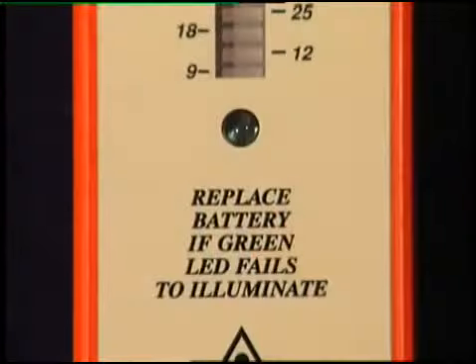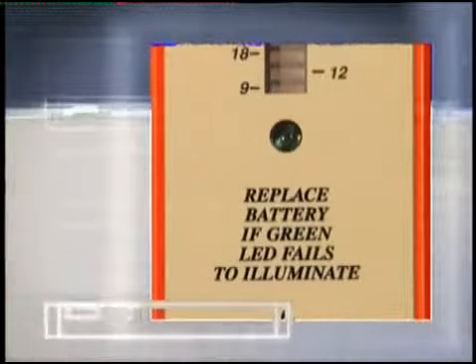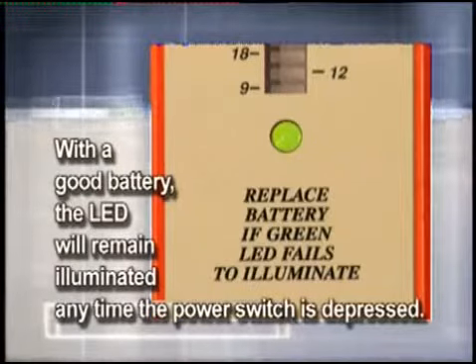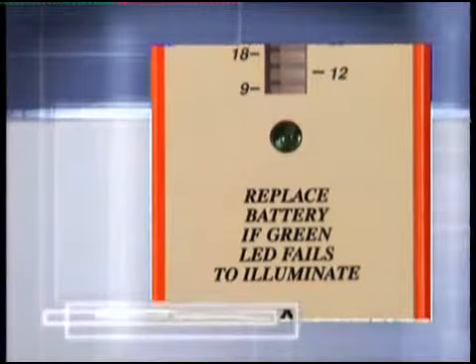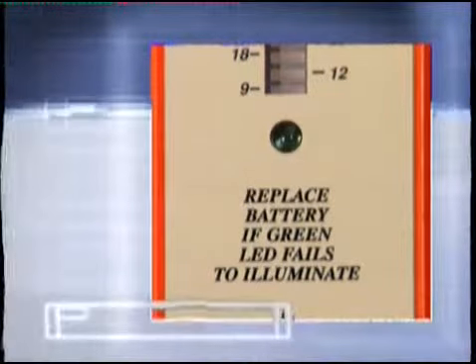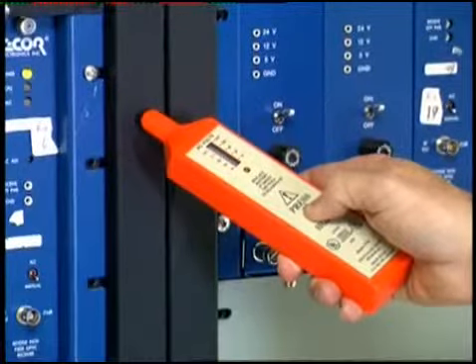The remaining indicator is a green LED located just below the bar graph window. This LED doubles as a power on indicator and a battery condition indicator. With a good battery, the LED will remain illuminated anytime the power switch is depressed. When the LED fails to illuminate, the battery must be replaced. You are now ready to test.